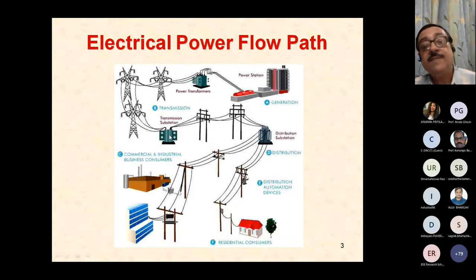So you have different types of systems. And these voltage ratings are important for us to know, because if we have to connect something in the transmission line area, even at the end of the transmission line, our power electronic system has to be rated at those hundreds of kilovolts, which is not easily possible directly. Even if we go in for the primary distribution system, 33 kV or 11 kV, our existing power electronic devices do not provide an economical solution. I did not say they do not provide a solution. Mark my words, I said they do not provide an economical solution for direct connection here.